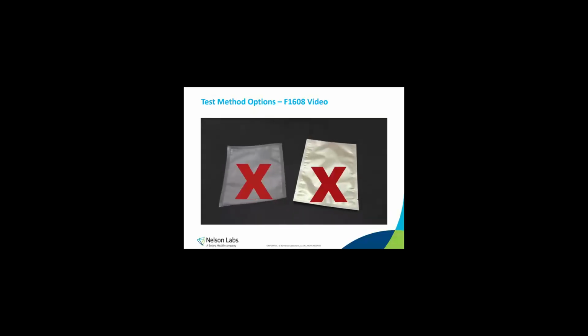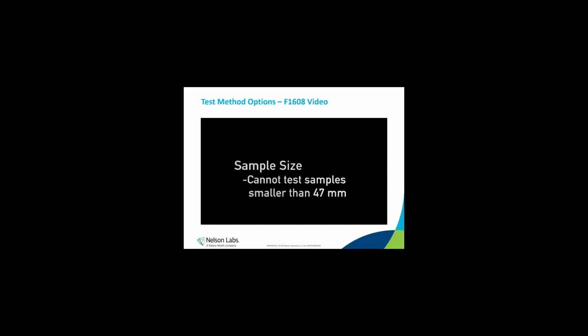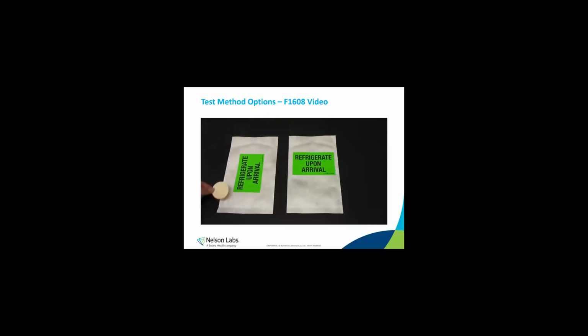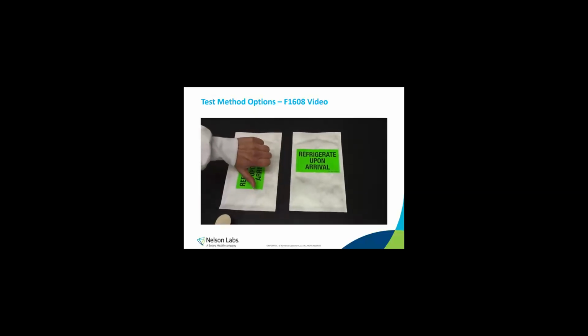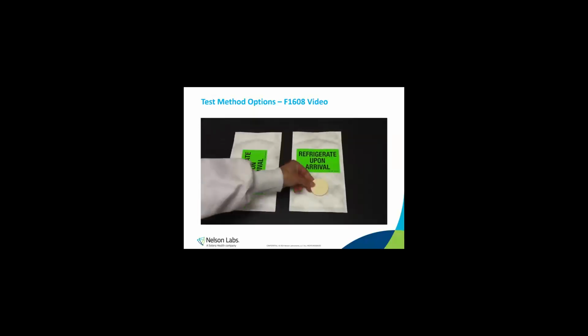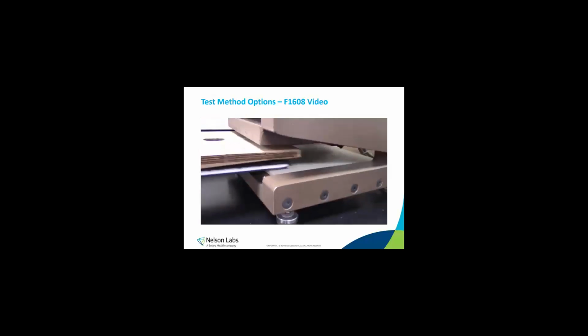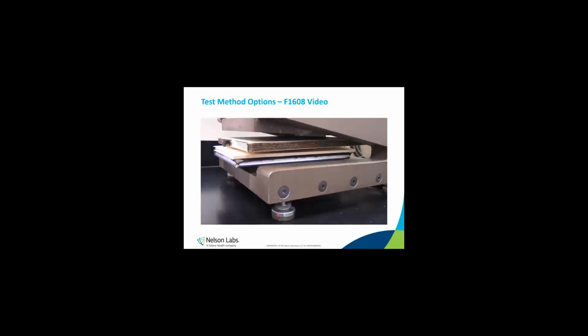Now let's look at our test videos. Here is the F1608. Okay, this is for porous materials only. So we can't use non-porous materials like foils or films. And because we're required to have a 47 millimeter disc, we need to make sure that we have an area that is not including the seal and not including any labels. And you can see here with my identical packages that it may make a difference how your labels are placed.